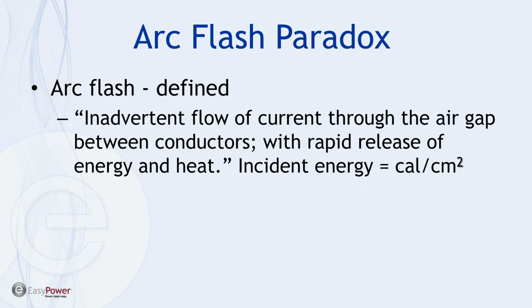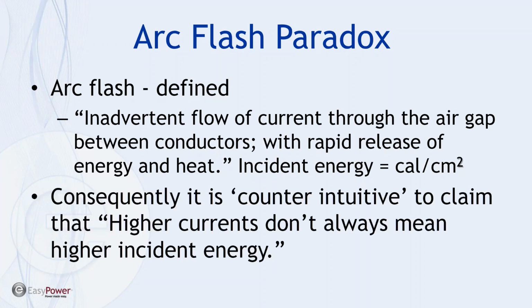And that unit of measure, that product of that calculation, is referred to as incident energy, and the unit of measure is calories per square centimeter. Now, with that definition, you might be surprised to hear that it's counterintuitive to claim that higher currents don't always mean higher incident energy. I refer to this as the arc flash paradox.